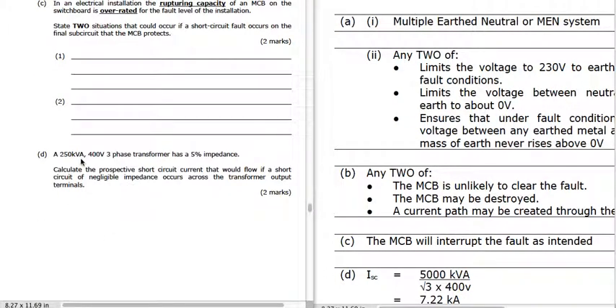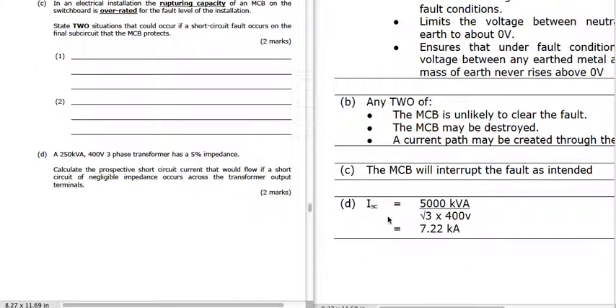We've got a 250 kVA, 400-volt, three-phase transformer with a 5% impedance, and we need to calculate the short-circuit current. We get the short-circuit current using: kVA divided by impedance — 250 divided by 0.05 — giving us 5,000 kVA. Then divide by √3 times 400, which gives us 7.22 kiloamps.